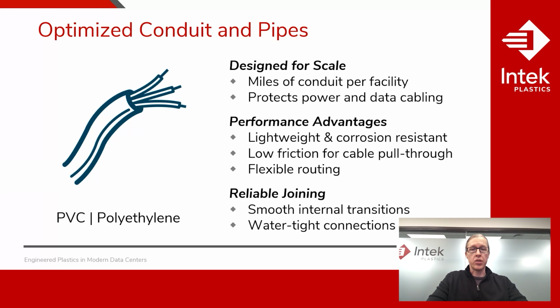Another critical feature of plastic conduit systems is how individual sections are joined. Proper joining allows separate lengths to be connected while maintaining a smooth internal pathway, minimizing hang-up points that can slow down installation or damage cables. For PVC systems, we often see solvent welding as a commonly used option. This creates strong watertight joints. Polyethylene systems are often joined using ultrasonic or spin welding. This produces a continuous uniform bond. These joining methods help create long, uninterrupted runs that support both performance and durability. These are both operations that Intek can perform in-house as a service for our customers. Together, material selection and joining methods make plastic conduit and piping systems a scalable and reliable solution for modern data center infrastructure.